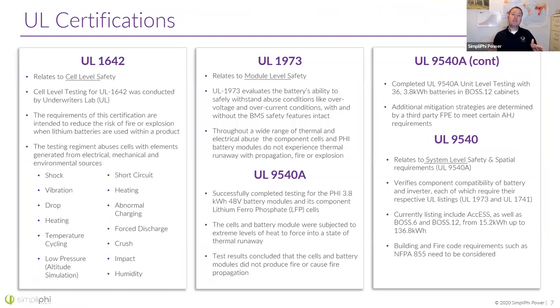We all start at the UL 1642 listing. This is at the cell level, right? They take one of our battery cells and subject it to an abusive regimen of tests: shock, vibration, abnormal charging, forced discharge, crush, impact, humidity. If we're able to maintain that cell's integrity, we take the cells and put them into packs, and put these packs into modules. The module is the battery itself, you could think of. Then we repeat those same tests, shock, vibration, drop, heating, etc., at the battery module level.